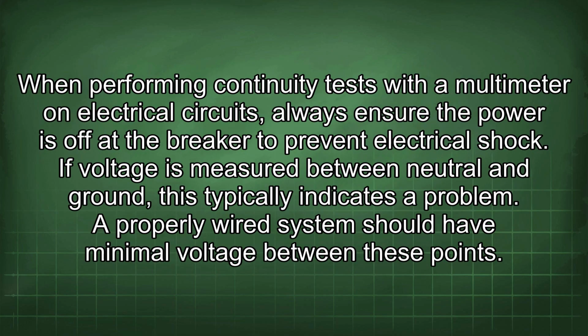When performing continuity tests with a multimeter on electrical circuits, always ensure the power is off at the breaker to prevent electrical shock. If voltage is measured between neutral and ground, this typically indicates a problem. A properly wired system should have minimal voltage between these points.